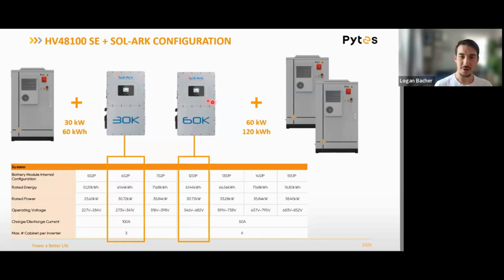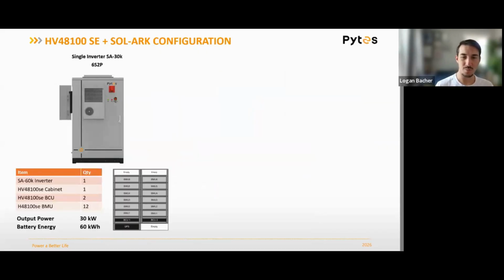On the 60K Sol-Ark, we can connect more batteries in series. So you'd use a 12S1P configuration instead. That's 12 batteries as one group. And look at the similarities, right? Both it's the same amount of energy, both it's the same amount of power. So again, to unlock that 60 kilowatts from this inverter, you just need to have 2 cabinets, one cabinet to each input of the inverter. This one, it's just one cabinet, but there's actually 2 battery groups, or more specifically 2 control units inside that still satisfy both of those inverter inputs.